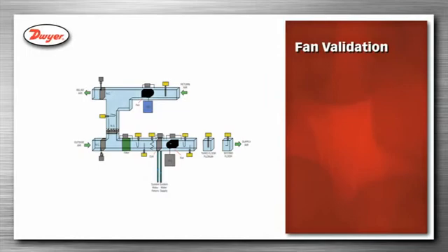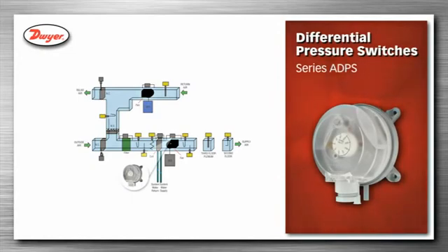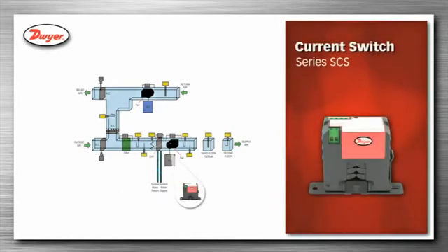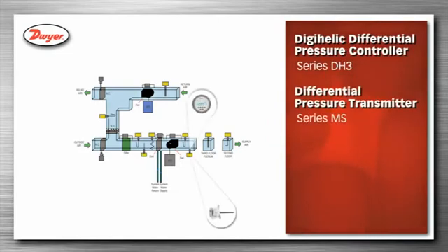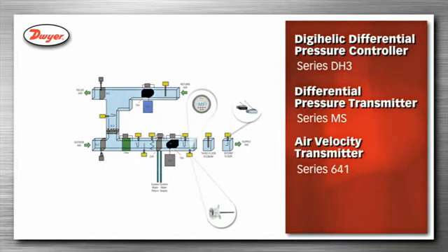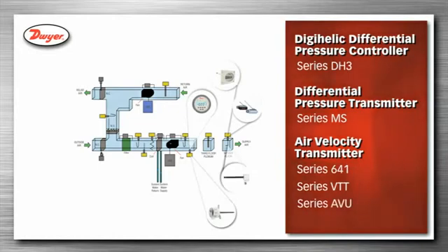Dwyer offers several products that can be used for fan validation, proving that the fan is operating. The differential pressure switch, series ADPS, can be used by monitoring the differential pressure of the fan. Series SCS current switch can be used by monitoring the current usage of the fan. Series DH-3 Digihelic differential pressure controller, series MS differential pressure transmitter, series 641 air velocity transmitter, series VTT air velocity transmitter, or series AVU air velocity transmitter can be used by monitoring the fan air flow or air velocity exiting the fan.